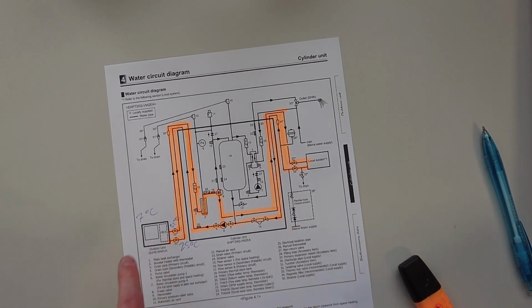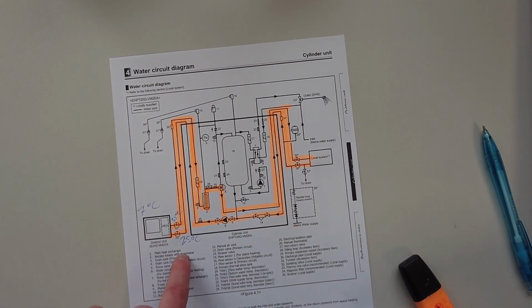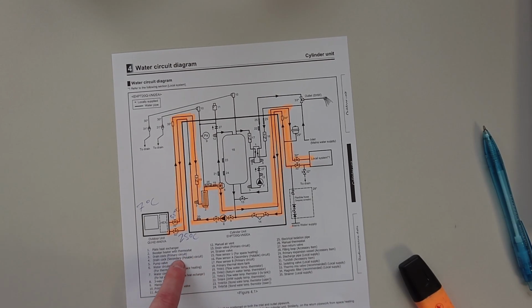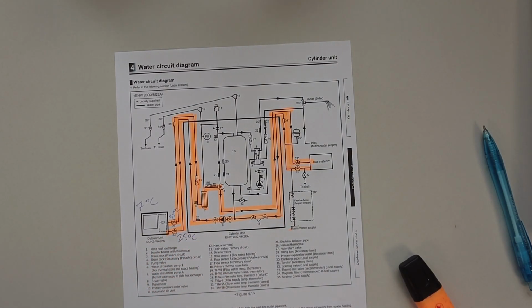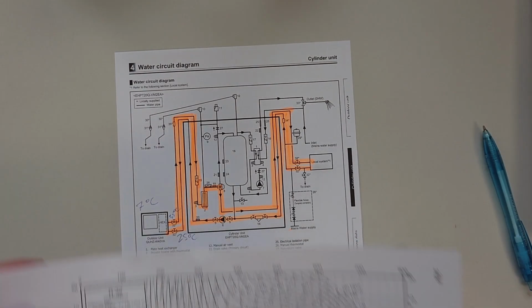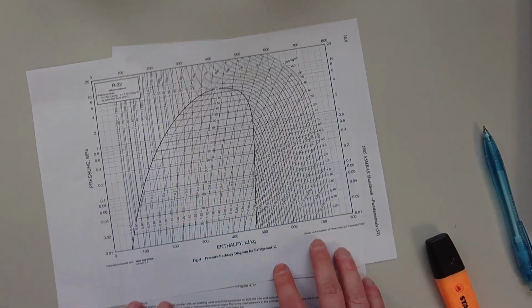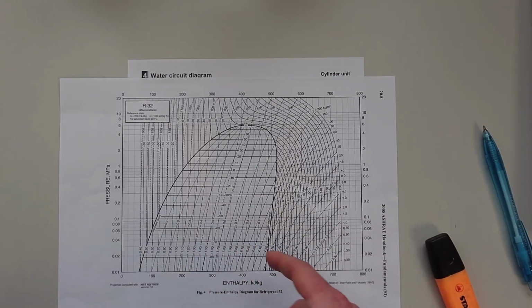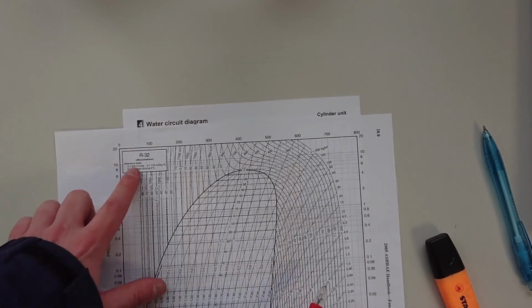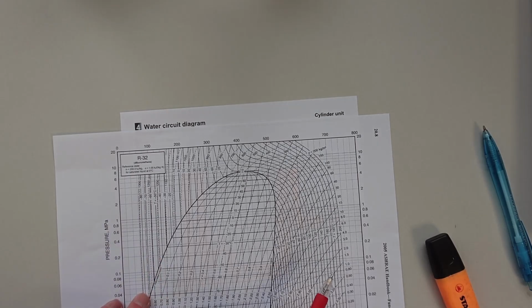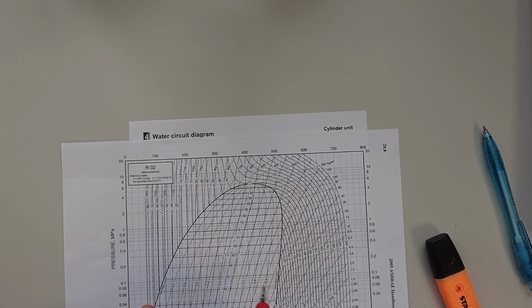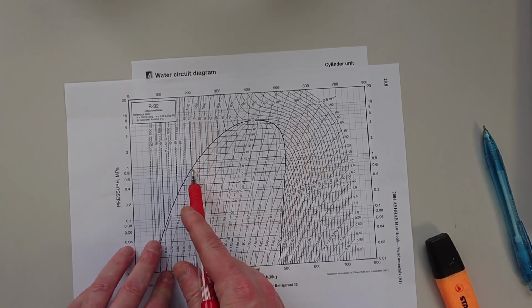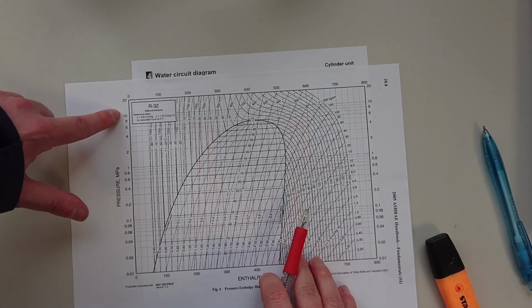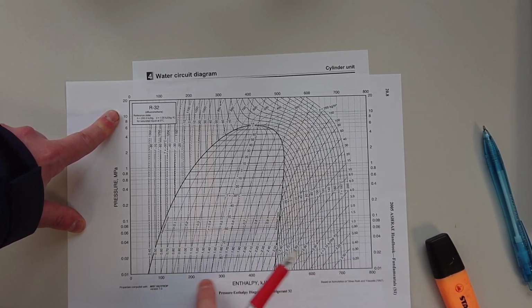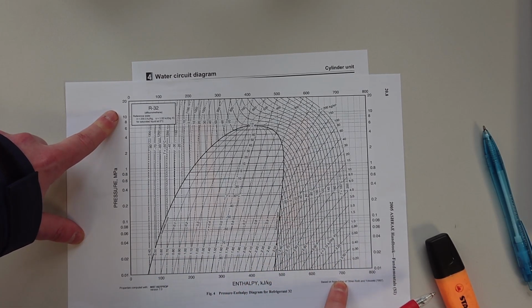So, what happens if we need more delta T here? Well, if we look at this pH diagram, which, again, if you don't know, go and look at another video, I'll have it on there somewhere. We're using R32, which is quite a common heat pump refrigerant in the UK, and it could well be the gas that you have. And if we say it's 0 degrees outside, we're sort of here. And all this has got is pressure up here and enthalpy, which is a measure of specific internal energy, across the bottom.